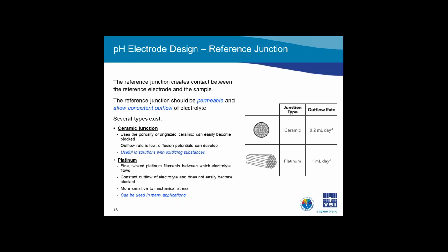The platinum junction consists of fine, twisted platinum filaments between which electrolyte flows. This junction type features a constant outflow rate of about 1 milliliter per day, and it does not easily become blocked. Care should be taken when cleaning this type of junction, as it is susceptible to mechanical stress. The platinum junction can be used almost universally, so it is the electrode I would recommend for most lab applications.